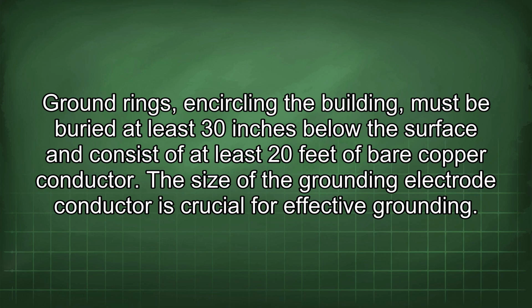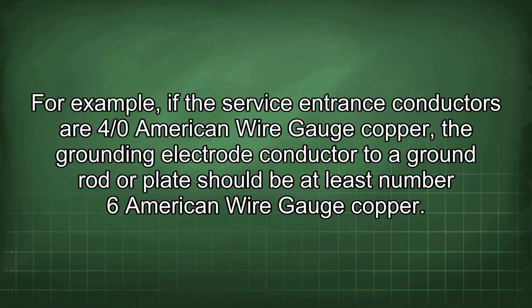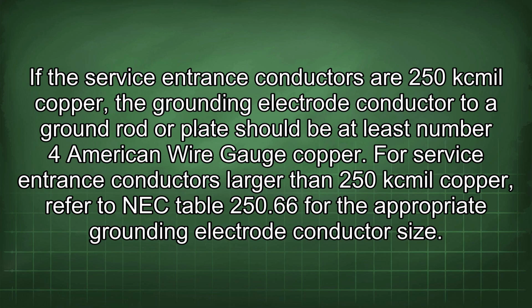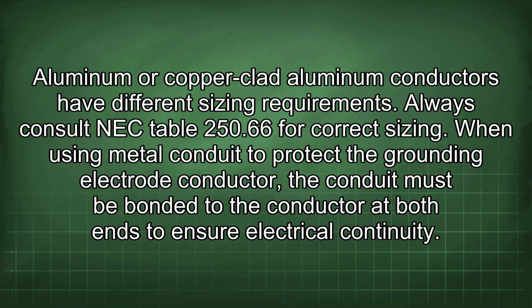The size of the grounding electrode conductor is crucial for effective grounding. For example, if the service entrance conductors are 4/0 American wire gauge copper, the grounding electrode conductor to a ground rod or plate should be at least number 6 American wire gauge copper. If the service entrance conductors are 250 kcmil copper, the grounding electrode conductor to a ground rod or plate should be at least number 4 American wire gauge copper. For service entrance conductors larger than 250 kcmil copper, refer to NEC Table 250.66 for the appropriate grounding electrode conductor size. Aluminum or copper-clad aluminum conductors have different sizing requirements. Always consult NEC Table 250.66 for correct sizing.